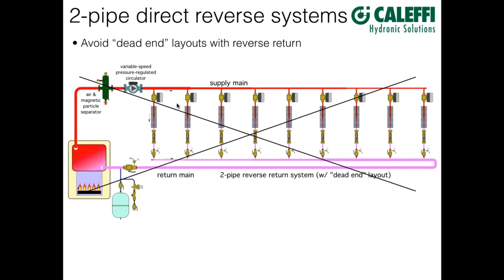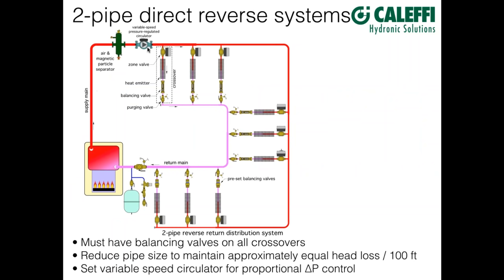Something to avoid is a dead-end reverse return. The first crossover on supply is the last on return, but the return has to go all the way out to the end, make a U-turn, and come back. The problem isn't that it doesn't work — it's that it adds significantly to piping cost because you need the largest piping size all the way from the far dead-end back through your heat source. Stay away from dead-end layouts. The best layouts involve making a loop — typically around the perimeter of the building.